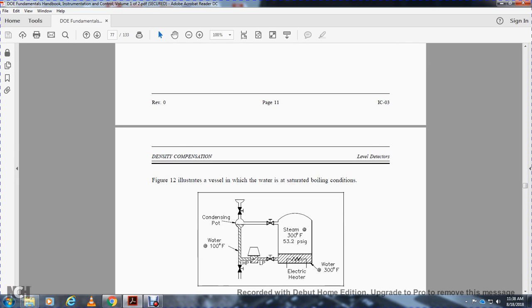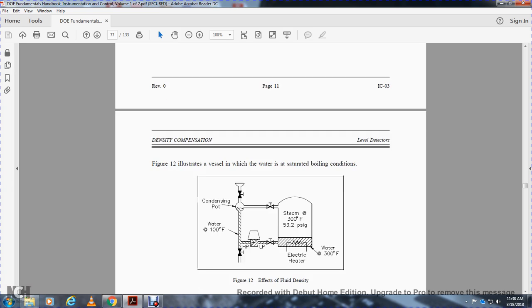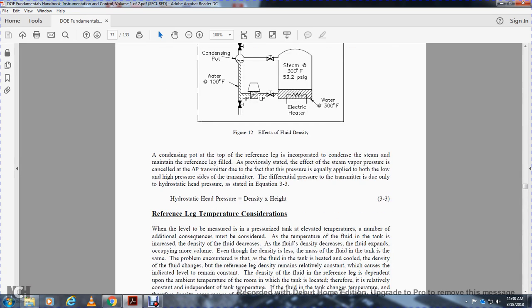Figure 12 illustrates a vessel with water in a saturated boiling condition. Condensing pot, water at 100 degrees Fahrenheit, high and low pressures. Steam at 300 degrees Fahrenheit, 53.2 psig. An electrical heater with a resistor heats the water to 300 degrees. A condensing pot is at the top of the reference leg.